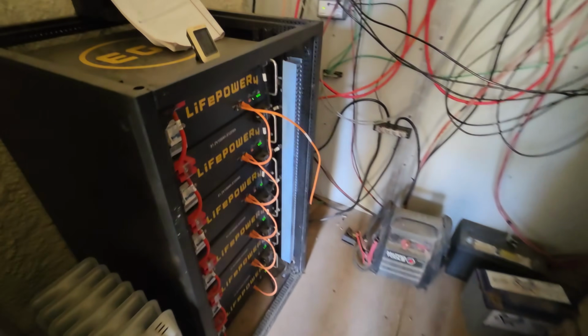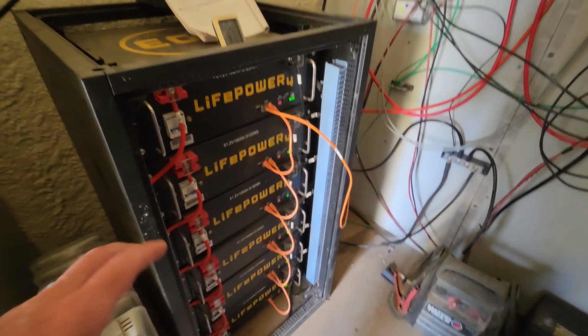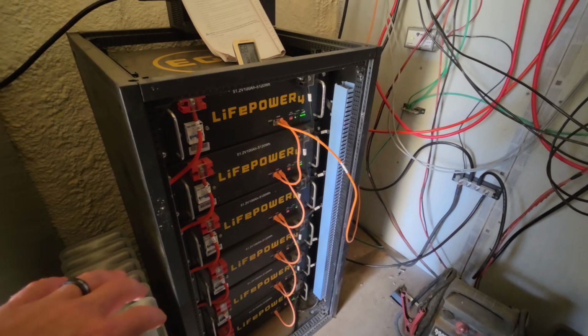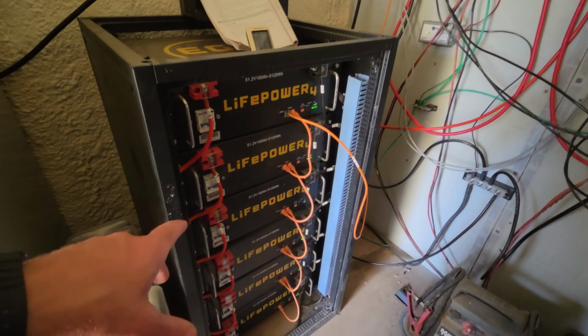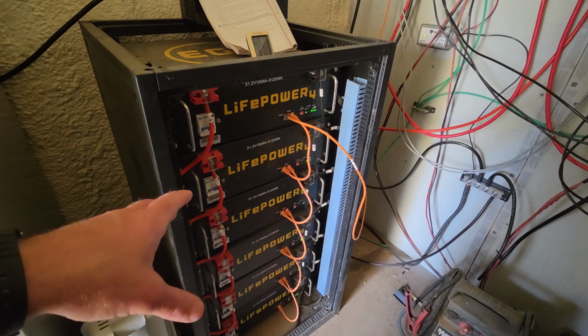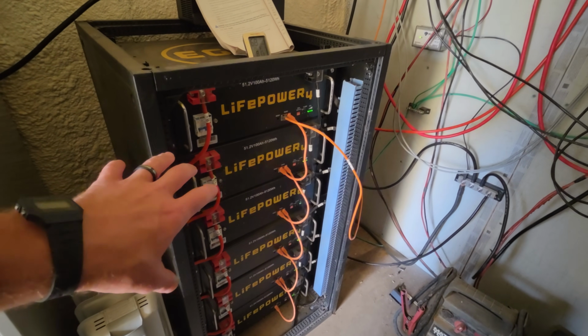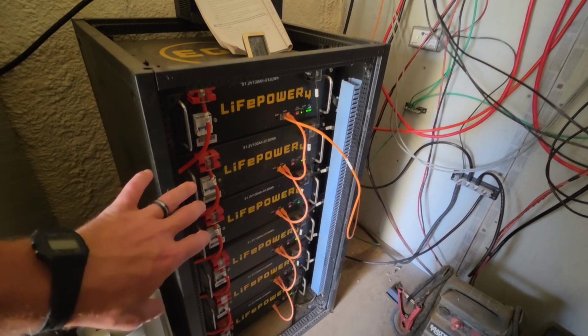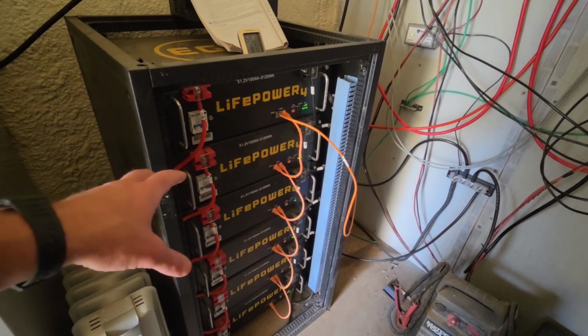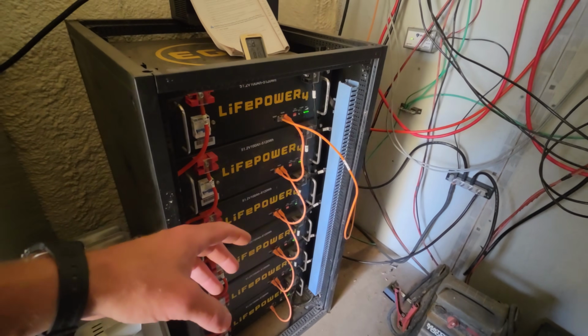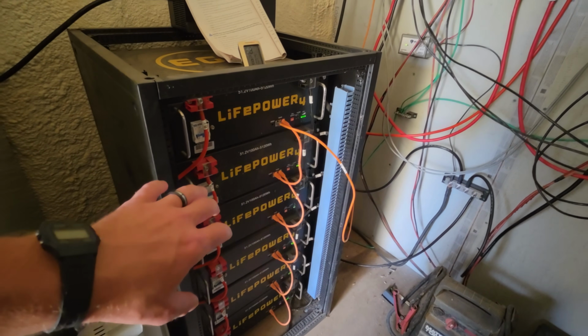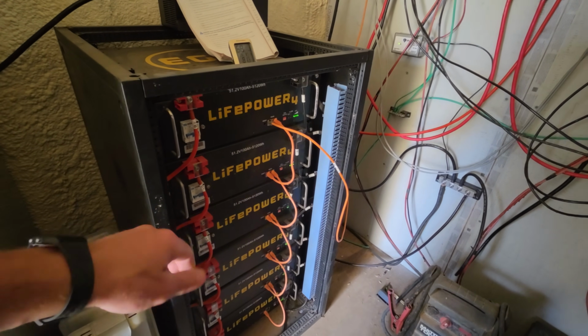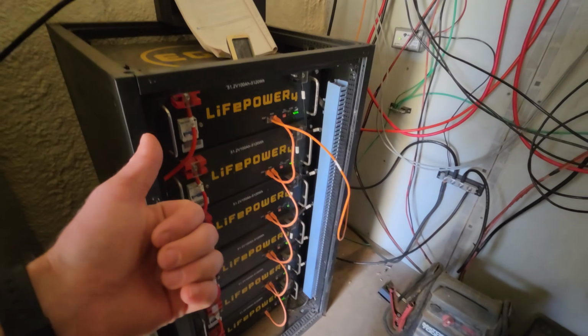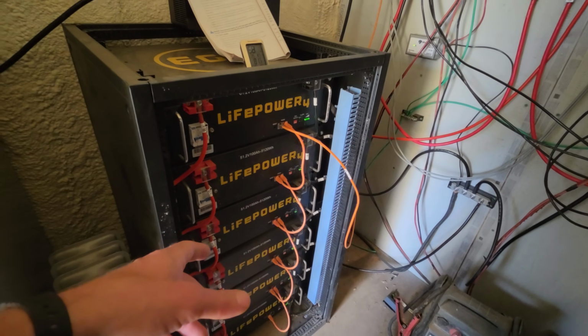What we're going to do is tie this into the main system. Right now I've got 6 of these server rack EG4 LiFePO4 batteries, each 48 volt, 100 amp hour. I'm going to add 50% more battery storage. We're sitting at about 30 kilowatts right now, and this will put us at 46 once we tie in this 314 amp hour battery.